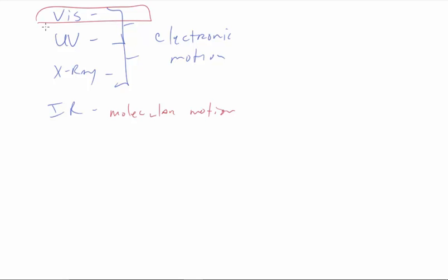and we will be working with light in those particular wavelengths of light, okay? Now, the other thing that we need to understand, if we go back to the drawing that you've got right above this, our detectors, and I kind of said this, but I want to make sure that you understand it, detectors read transmittance, all right? They read transmittance. Now, a lot of these have computer programs that are part of the machine that actually will not spit out transmittance, but they will spit out an absorbance value. But I need you to understand the relationship here, all right?